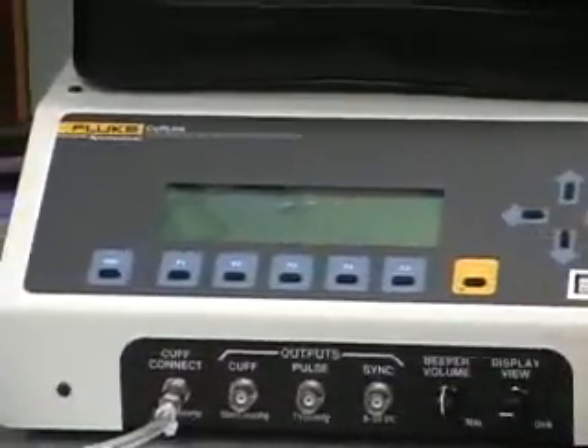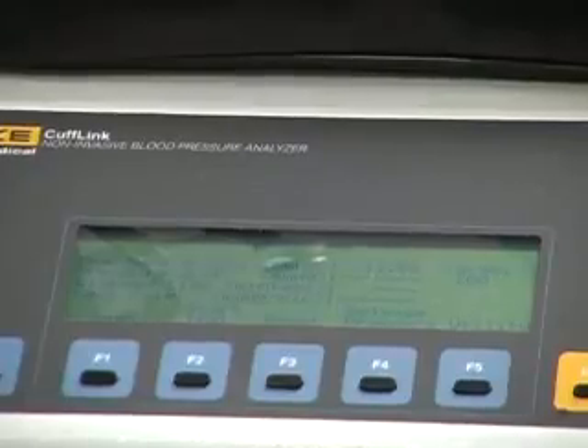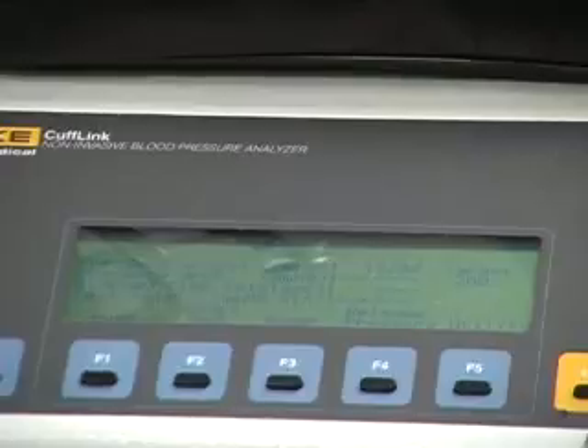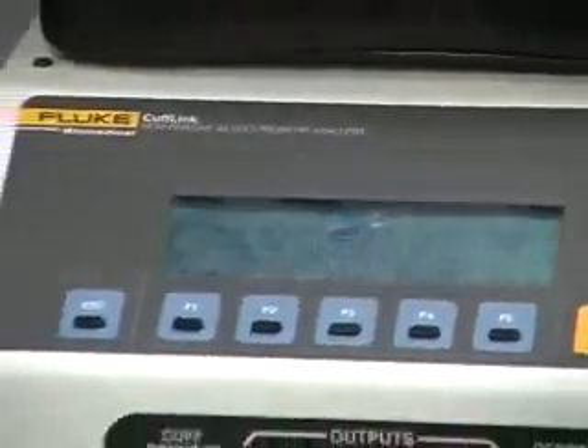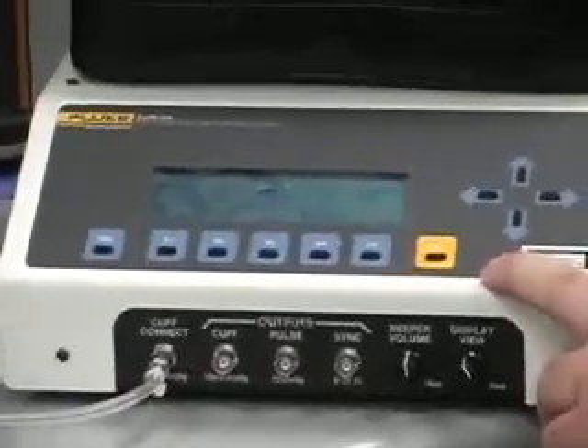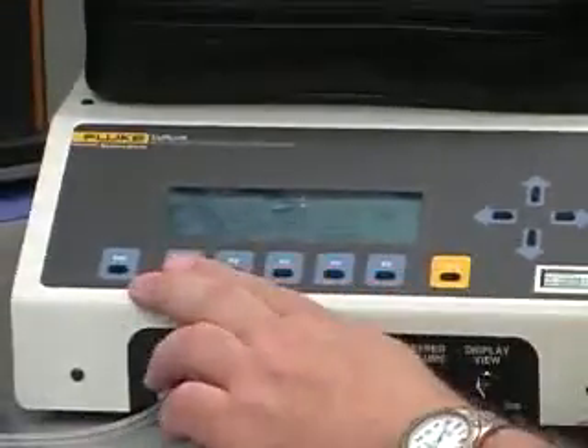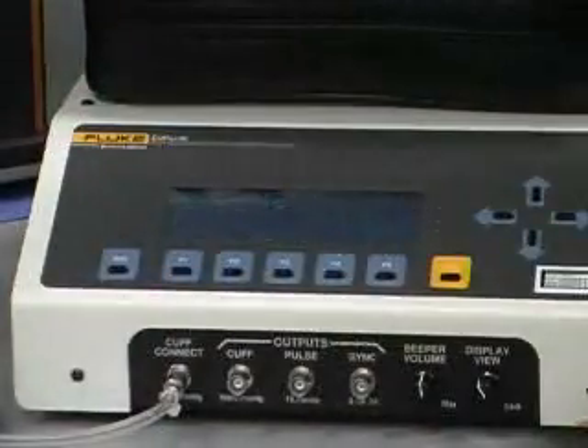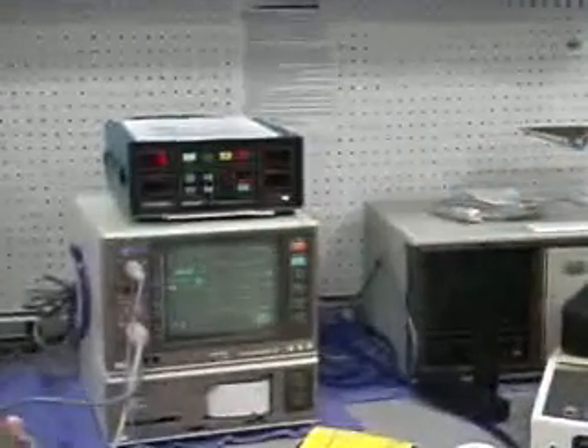Use the cursor to go up to leak test. Hit enter. And now what we're looking at is a target pressure of 200 millimeters of mercury. We want to inflate it till it gets over 200. Once it does, it stabilizes the reading, and the analyzer will display how much the pressure changes over a 1 minute time period, and it'll display it as a leak rate or a leak factor on the analyzer. So we just turn on the pump. Probably best bet, before you start this test, reset the diagnostic mode on the Criticon, because that will time out by itself. We want to make sure that that runs for a full minute.